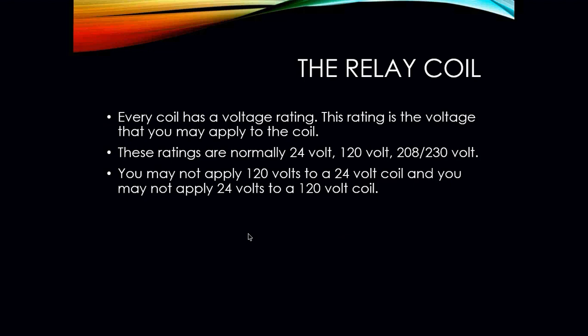Every coil has a voltage rating on it. These ratings are the voltage that you have to apply to the coil. These ratings can be anywhere between 24 volts, 120, 208, 230, you name it. However, you may not apply, say, 120 volts to a 24 volt coil. You may not apply 24 volts to a 120 volt coil. You can't do it. You have to put the correct voltage to the coil in order for the relay to work properly.